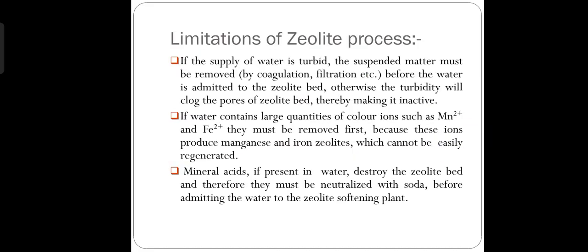Now coming to the limitations of the zeolite. Each and every process has some limitations. We have to follow those limitations, otherwise more vigorous problems may arise that may cause harm to the softener. Now what are those limitations? If the water supply is turbid, dhundla pani, the suspended matter must be removed first by coagulation, then filtration, before the water is admitted to the zeolite bed.